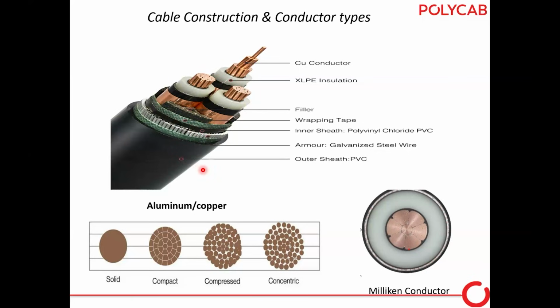These cables have different conductor sizes, sometimes solid, compact, compressed, and concentric. This is a copper cable. Instead of copper, aluminum can be there. Here, on the right side, if you see, it's a Milliken conductor. These Milliken conductors are used for EHV. A Milliken conductor is made of small thin wires. This is used to reduce the skin effect basically, and that's why it is extensively used for EHV.